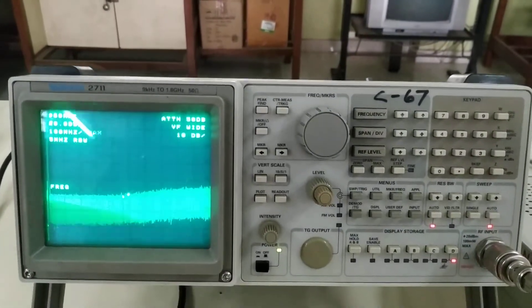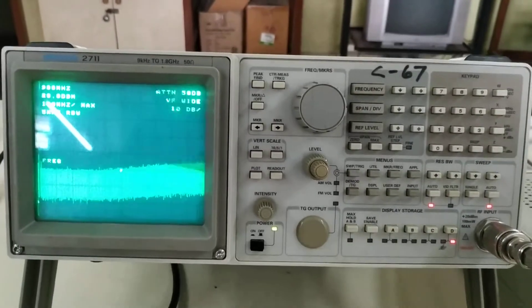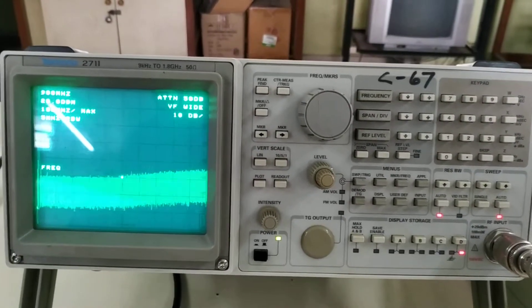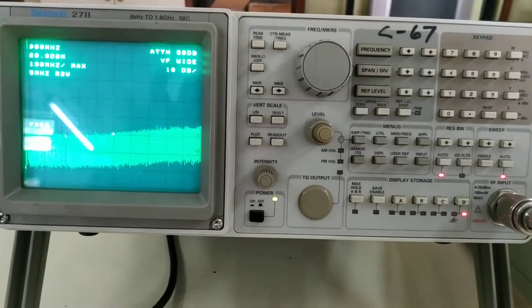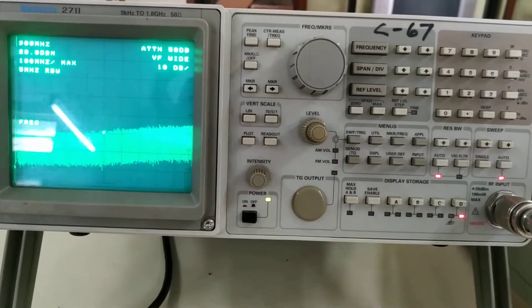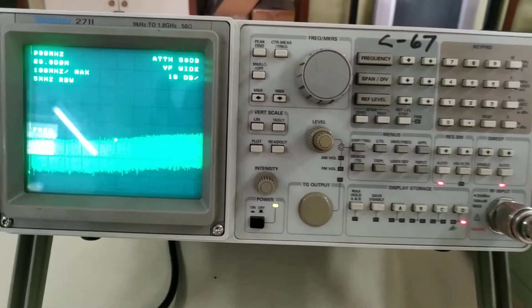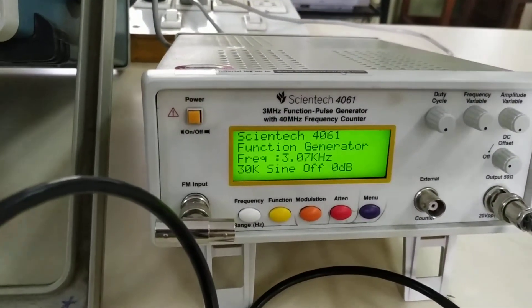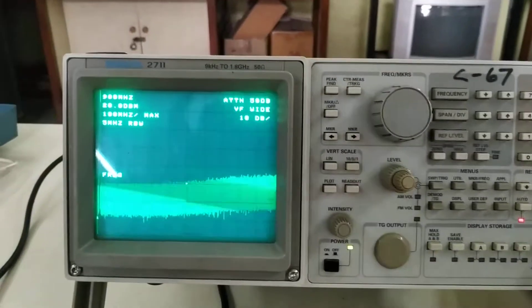Last time we already saw the signal generator front panel. Now this is related to the spectrum analyzer front panel. The front panel has quite a number of buttons, but we are not considering all of them — only whatever is useful to us. Right now I have selected a 3 kHz sine wave frequency that is given to the spectrum analyzer.